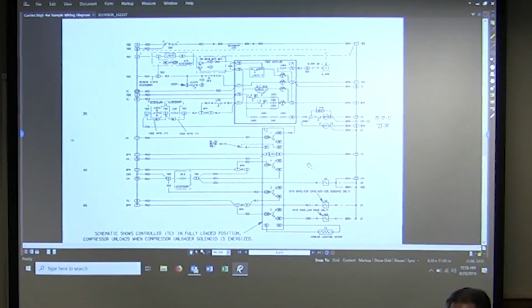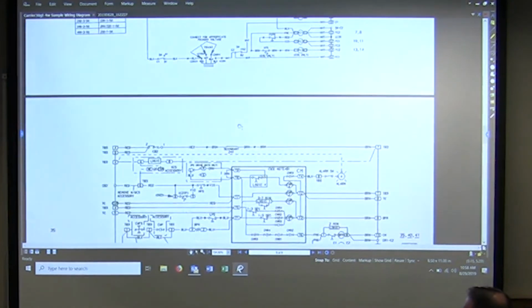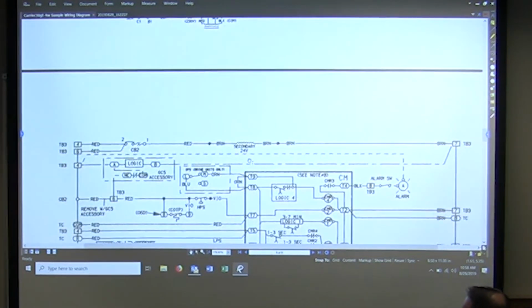Bring it to a control relay where we check status of the transformer fuses. Okay, so where do I want it? Here's our transformer up here. You're just checking power on the secondary side, so you can put a control relay in series right there and come off a contact, going back to the controller. Okay, so I've got a 1, a 2, a 4, and a 7 on this top. Where do I hook one side of, and what am I hooking? A relay coil, between 4 and 7. Okay, so I've got a 4 and 7.